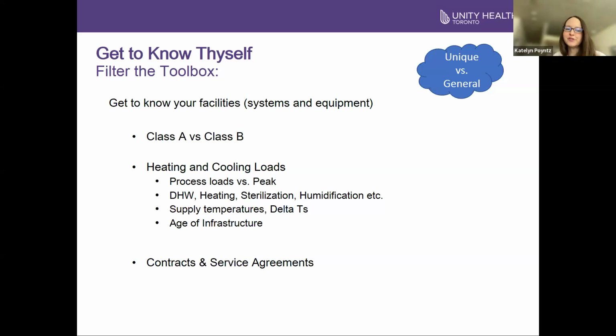Age of infrastructure also ties into your ability to upgrade existing systems. A quick example: people say install a VFD on a pump to save energy, but if your pumps are really old, you need to upgrade the motor first before you can install the VFD.